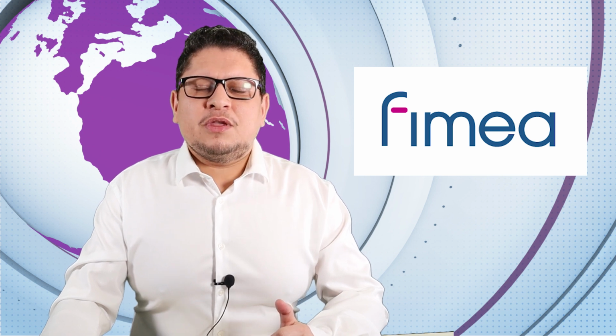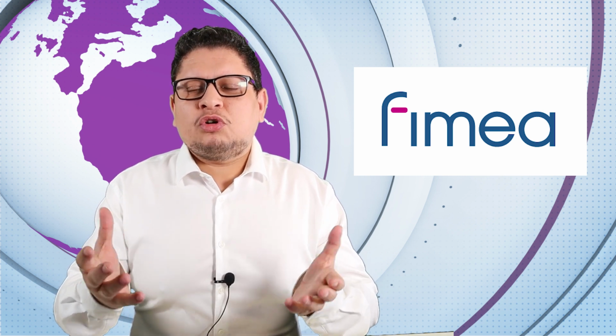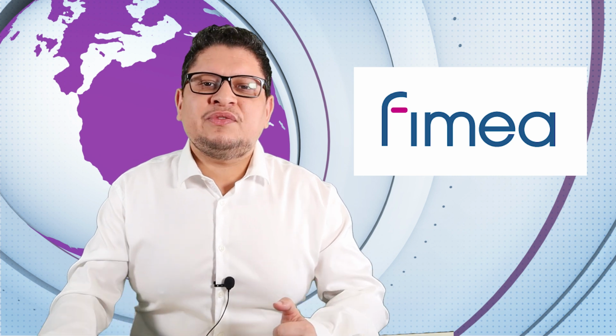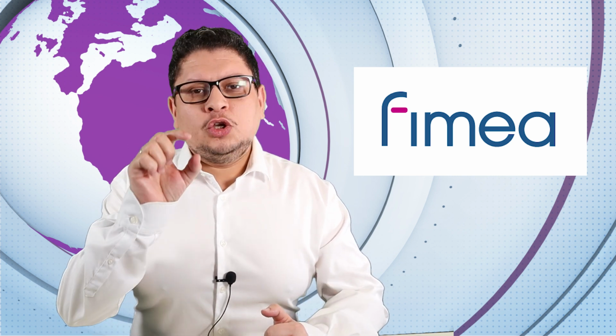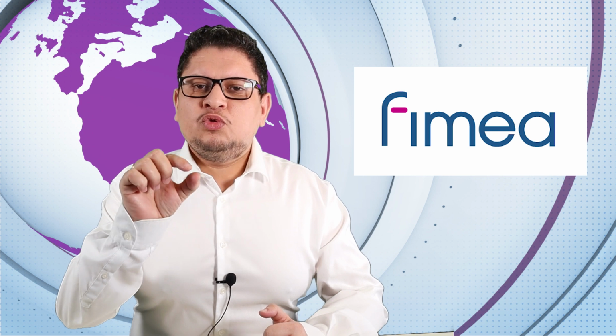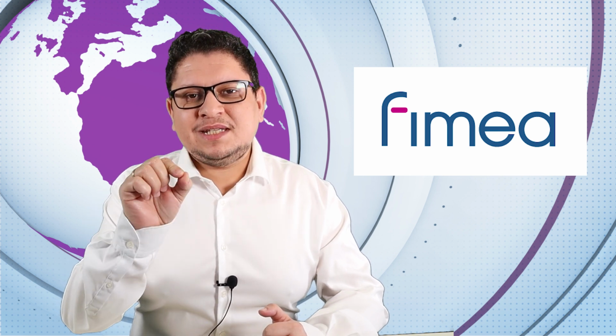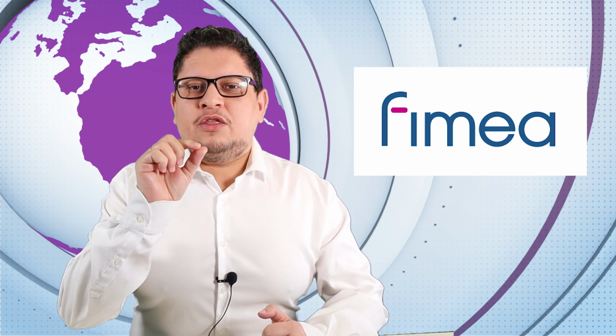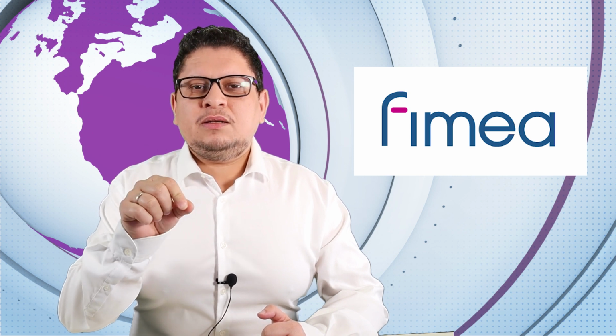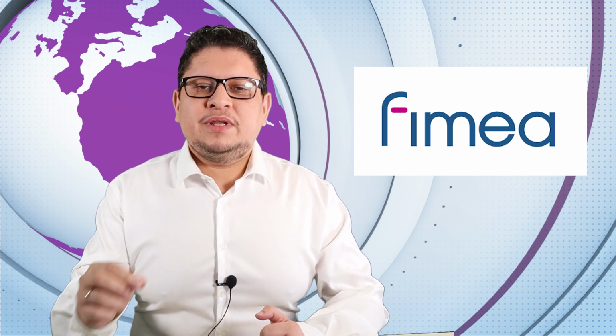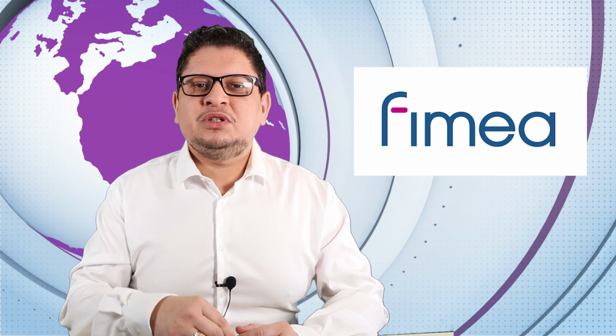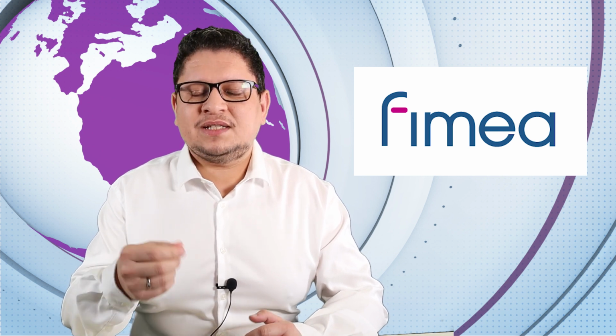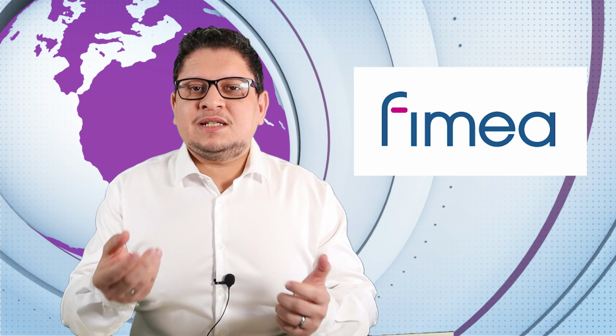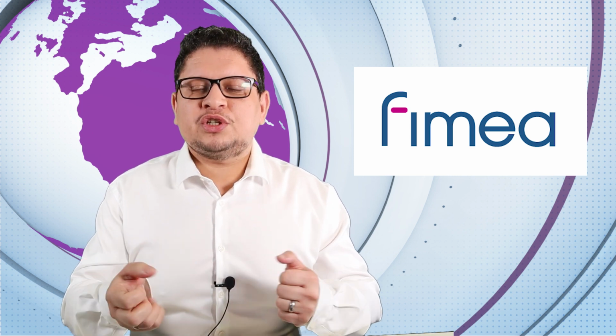To be able to recognize if a product is good for self-testing, normally you go on the box and look for the CE marking. If you see the CE marking with the notified body number, then you can say, yes, this product is good. This is certified by a notified body, so it's good for self-testing. When we say self-testing, it's testing by a layman, not by a professional.